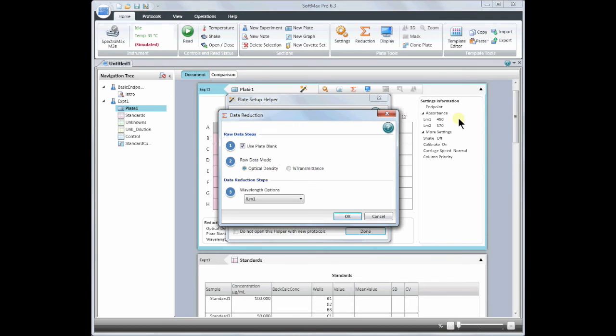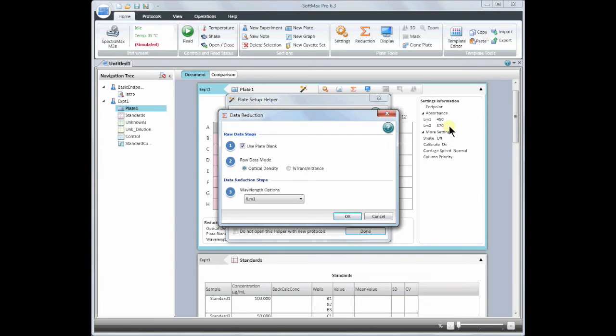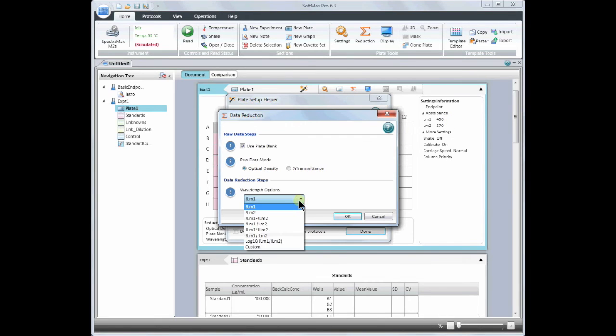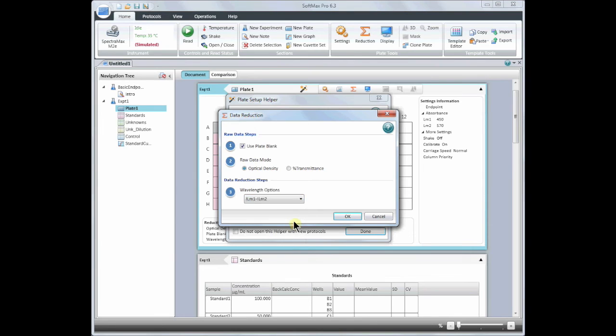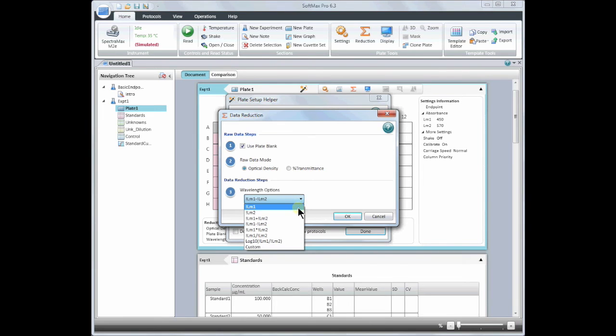LM1, or the first wavelength, is 450 nm and LM2, the second wavelength, is 570 nm. I would like to subtract the values from the 570 nm reading from the values from the 450 nm wavelength reading. To do this, click on the drop down menu and select LM1 minus LM2. All of these options in the data reduction window can be changed after you read a plate, so if you decide you want to have a different wavelength option, you can.